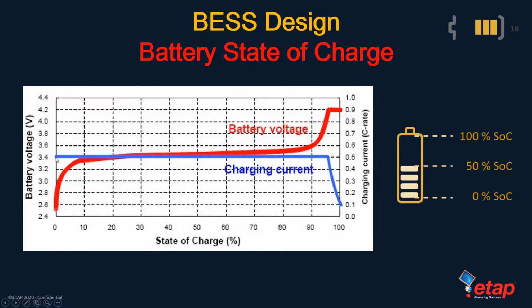Behind the scenes, the battery is being charged using a charging current, shown in the blue line, and it's usually constant current charge up to a certain state of charge, after which the constant current changes to a decaying exponential value. Correspondingly, the battery voltage rises as the charging current is applied, and it remains fairly constant voltage till the charging current starts reducing after reaching a preordained state of charge, and the battery voltage starts climbing and becomes constant, which is where we have reached 100% state of charge and the battery is ready to take on some load in the system.